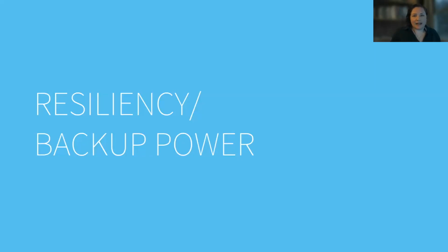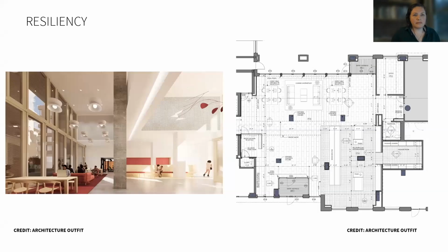Currently, the building has a gas-fired backup generator. Residential buildings over 125 feet require this backup power for life safety elements such as the elevator, fire pump, and emergency lighting. Unfortunately, the easiest and most economical solution at the moment is a gas generator. We have looked into battery backup power, which could draw from our solar panel arrays. But currently, the amount of battery power that would be needed to accommodate the startup loads of the elevators and fire pumps would require far more space than is typically available, and is prohibitively costly at the moment.